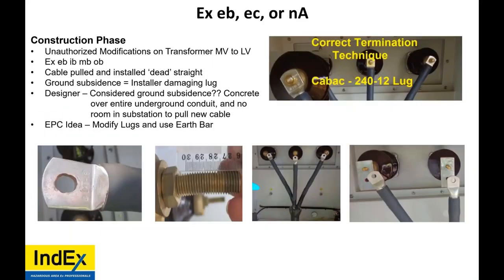Now, about transformers. If it's an oil-filled transformer, its terminal boxes are usually EC, EB, or NA. You might have pressurized, but you have to follow their instructions. Well, what happened on this one? There were unauthorized modifications. This was an EB, IB, MB, OB, so it had intrinsically safe devices on it. MB, well, it had that bus duct going into it on the other side. O, oil was in the main compartment, and then you had these insulated bushings.